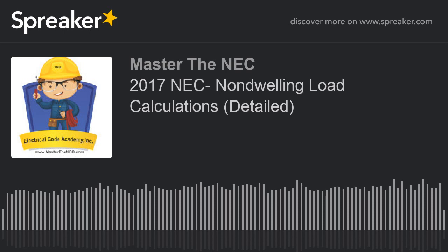We also want to remember some golden rules here. If we're going to run parallel conductors, and there's a chance we're not with this size service because it was way too small, but if we had a set where it was over 800 amperes and we decided to run parallel sets, then they can't be smaller than 1 aught, okay? And the parallel sets have to be joined at both ends in accordance with 310.10(H)(1) and all those rules with paralleling we have to take into consideration, okay?